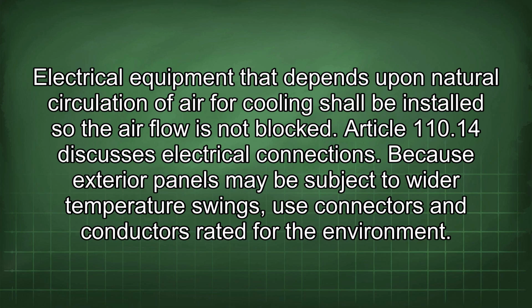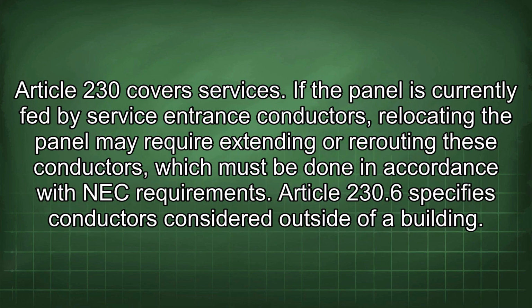Article 110.14 discusses electrical connections. Because exterior panels may be subject to wider temperature swings, use connectors and conductors rated for the environment. Article 230 covers services. If the panel is currently fed by service entrance conductors, relocating the panel may require extending or rerouting these conductors, which must be done in accordance with NEC requirements.